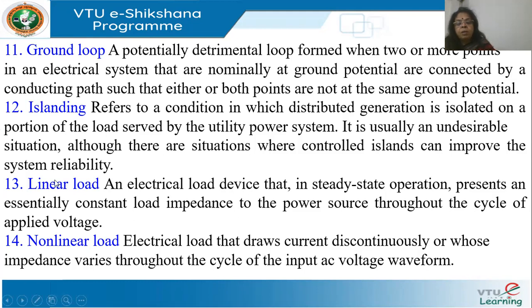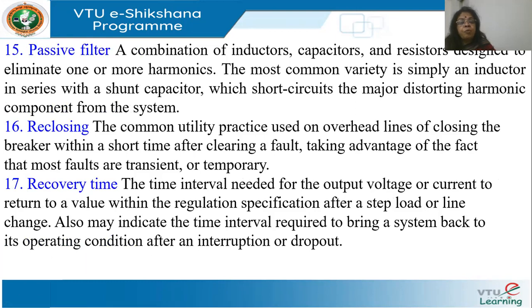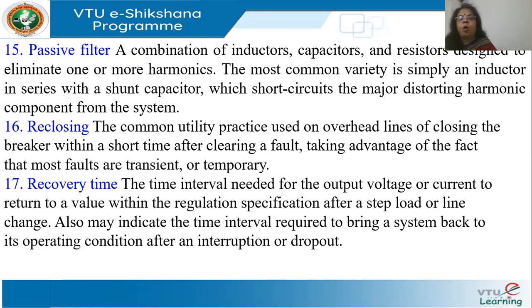A linear load is a device that presents a constant impedance to the power source throughout the cycle of the applied voltage. A non-linear load does not. A passive filter is a combination of inductors, capacitors, and resistors to eliminate one or more frequencies, whereas an active filter can be designed to eliminate all harmonic frequencies at one time — you can't do that with a passive filter, which requires separate filters for the third harmonic, fifth harmonic, and so on.